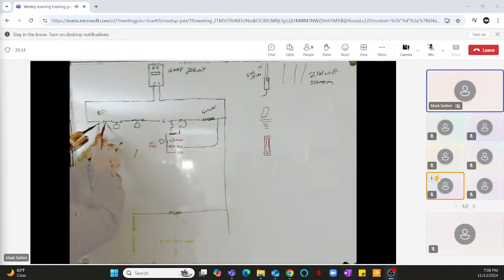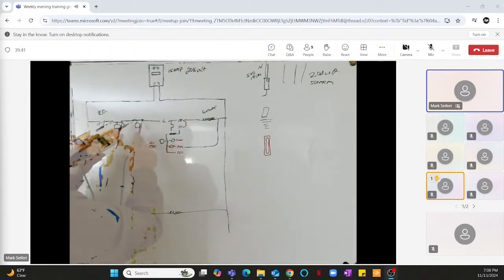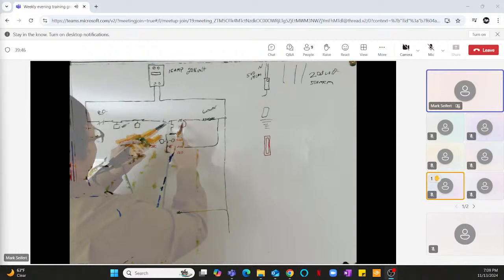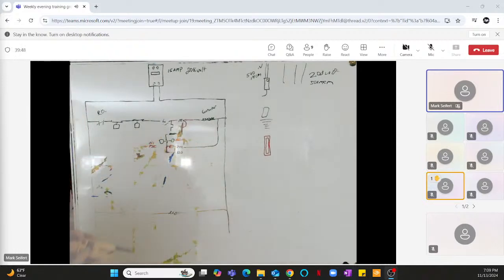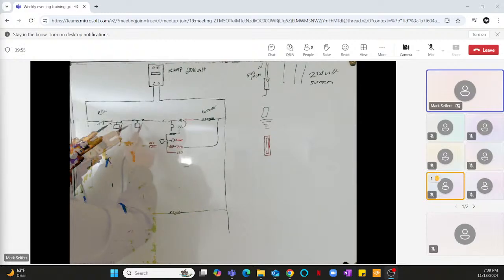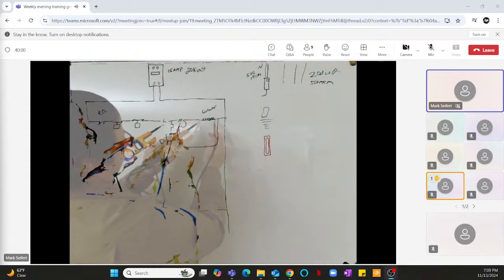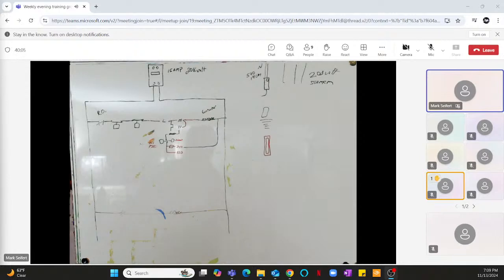Yes, I've got power. All right. Do I got power across my RO? Nope. Low pressure? Nope. High pressure? Nope. L and M? Yep. That's your open circuit. All right, let's do another one. RO? Nope. Low pressure? Nope. High pressure? Nope. L and M? Nope. What the hell? I got power there. It's not pulling in. I got a bad contactor. Okay.